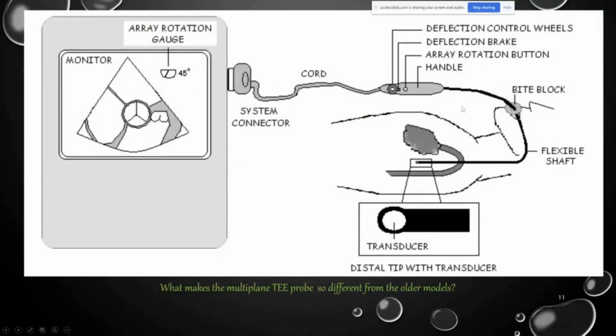So this is what it looks like in your book. So the biggest difference between the omniplane and the biplane and single plane is that the omniplane has an array rotation button, this button right here, and that is located on the handle of the probe itself. So this allows, instead of the sonographer having to do the switching, the physician can do the switching himself. And it allows that physician to be able to rotate that ultrasound beam from 0 to 180 degrees, and it allows for easy access to every plane that's located between that horizontal and the longitudinal plane. So the array rotation gauge right here is on the monitor, and it tracks that exact position in degrees. So it's always easier for the doctor to be able to just look up at that screen.